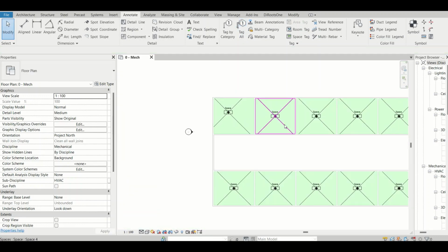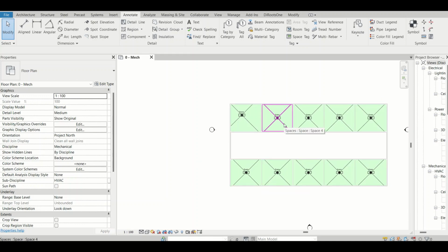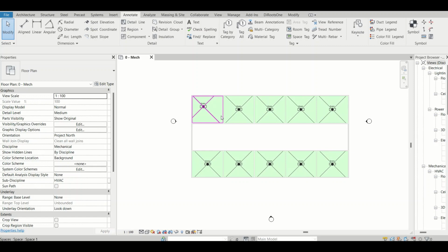Perfect. Now, the point is, what is a zone and how is it different from spaces. So, for example, you are an HVAC guy, and you know these 5 rooms at the top level all have the same dimension, same volume, and same HVAC calculations, and you can control all these rooms by one thermostat. So why should you calculate each and every time for these five rooms or spaces separately?